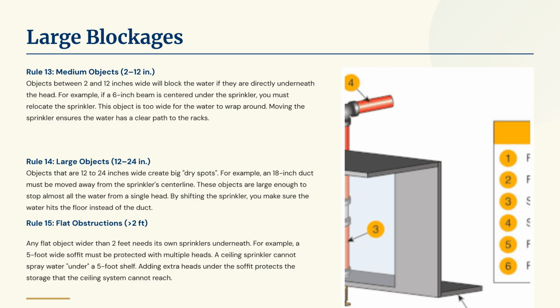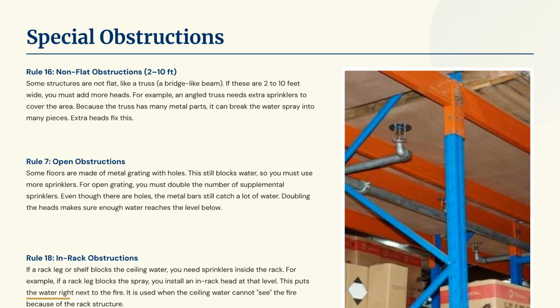Rule 13 requires relocating sprinklers away from medium objects, 2 to 12 inches wide, if centered underneath. Rule 14 focuses on large objects, 12 to 24 inches wide, requiring sprinklers to be shifted away from the center line. Rule 15 mandates separate sprinklers underneath flat obstructions wider than 2 feet. Rule 16 requires extra heads for non-flat obstructions, such as trusses, between 2 and 10 feet wide.